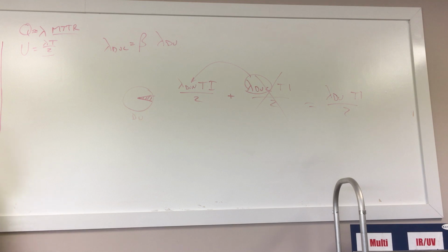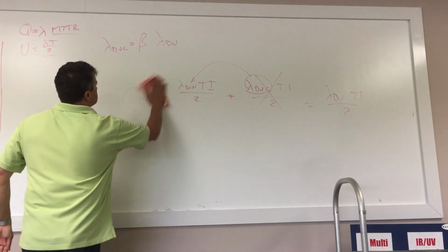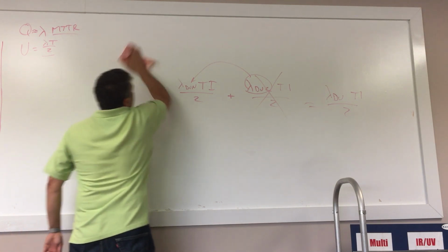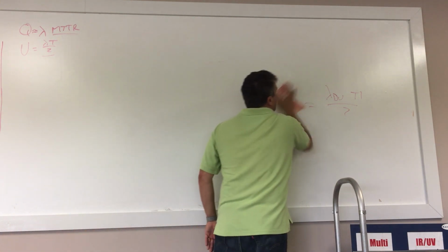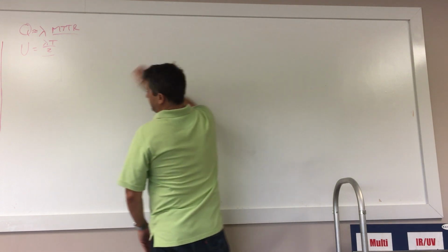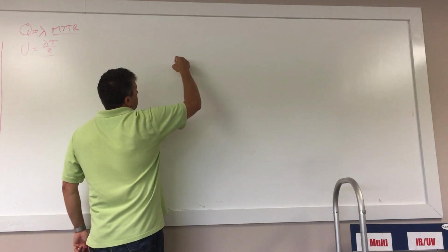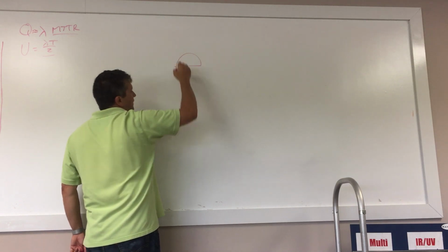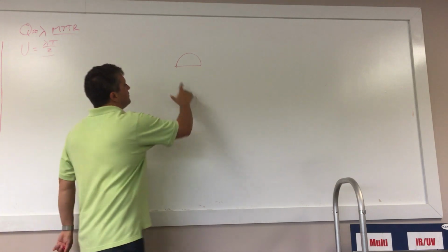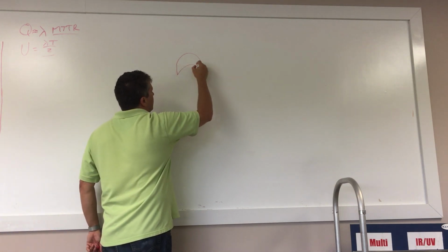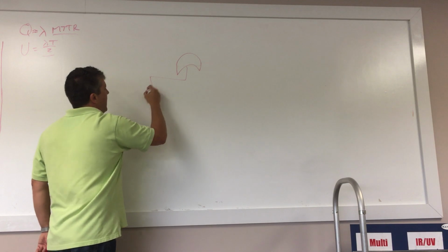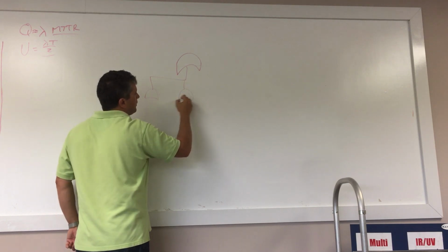Now, 2 out of 3. The only term that I'm going to deal with for 2 out of 3 is the du term, because the same kind of thought processes apply to everything else. So with 2 out of 3 voting, and let me simplify the fault tree to some degree, I am going to have an OR gate with 3 AND gates under it.